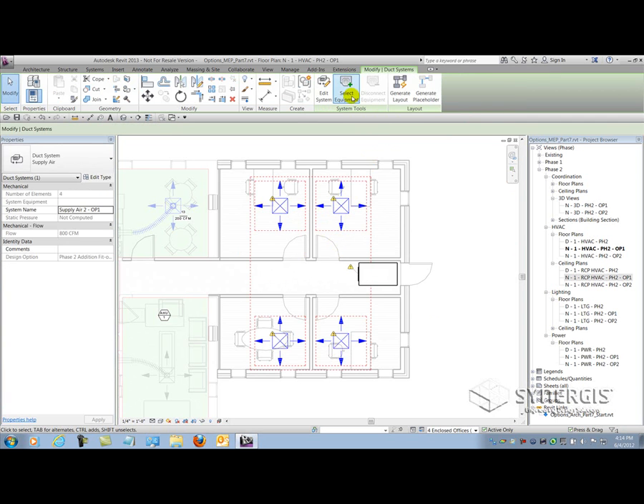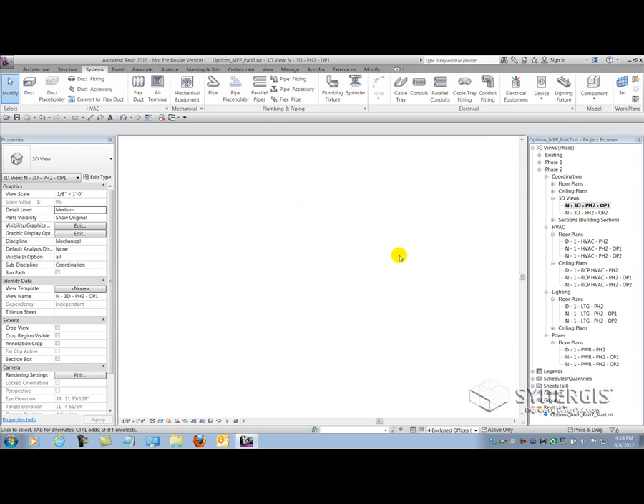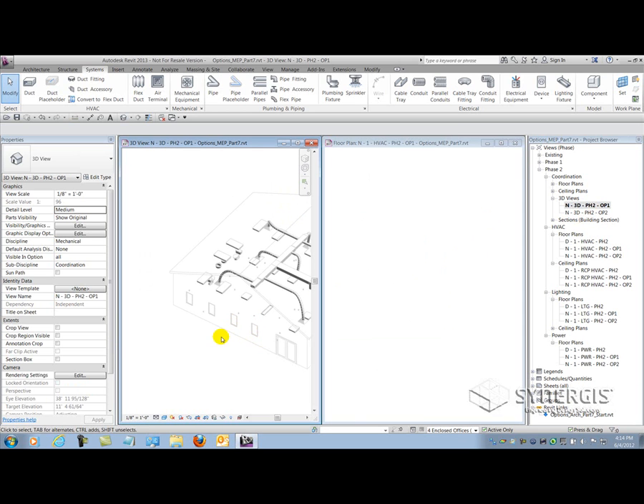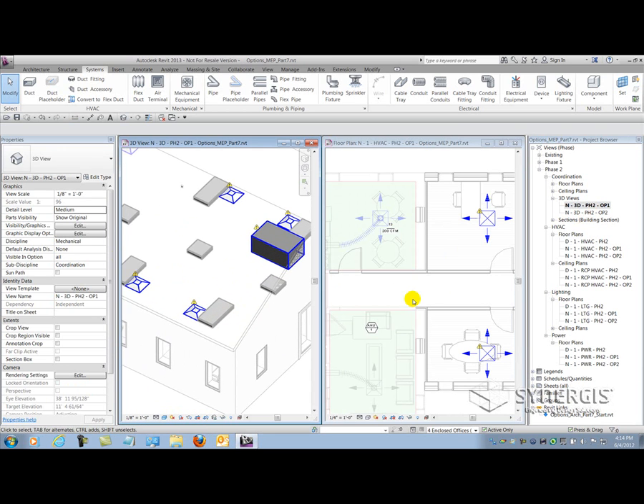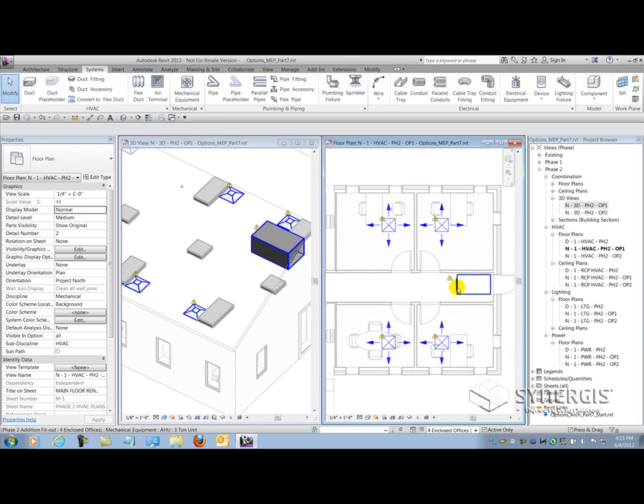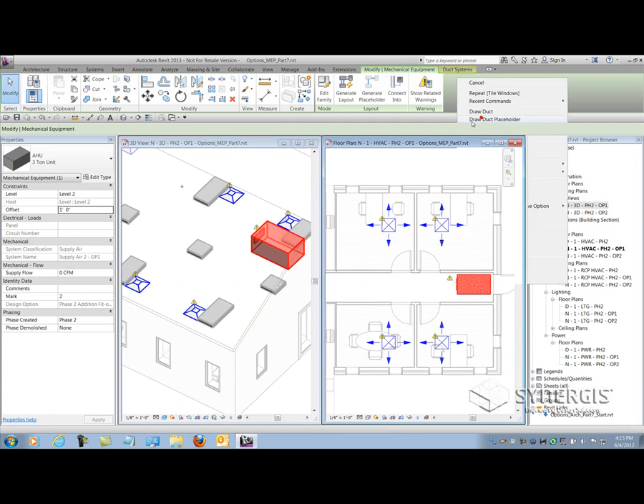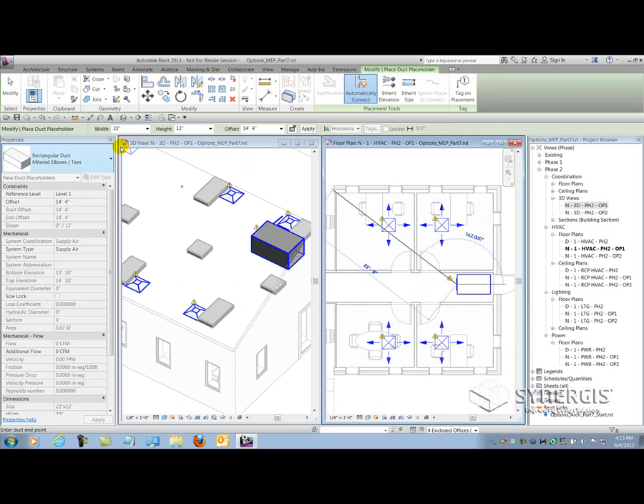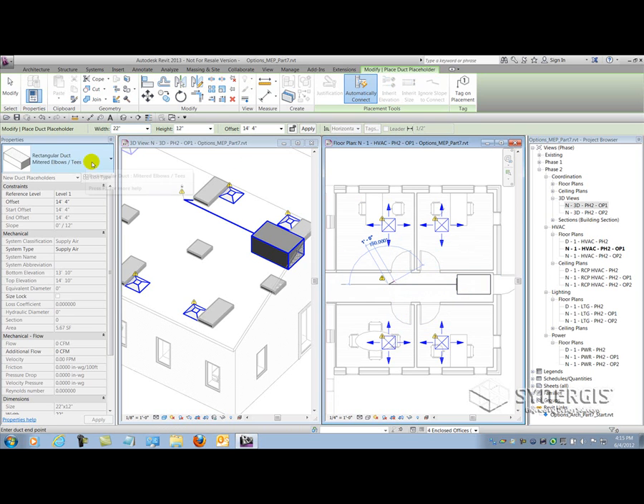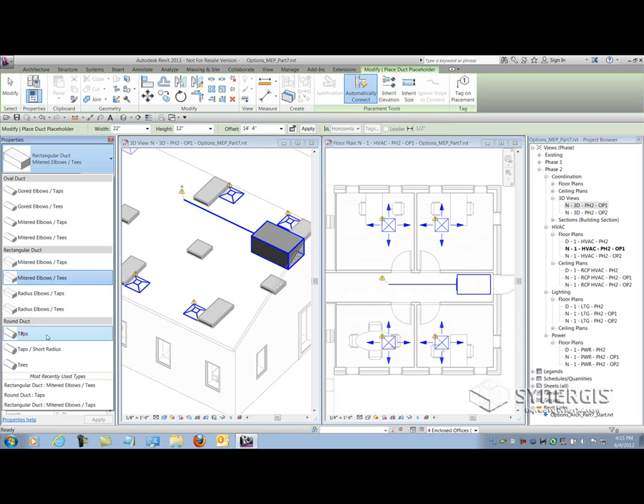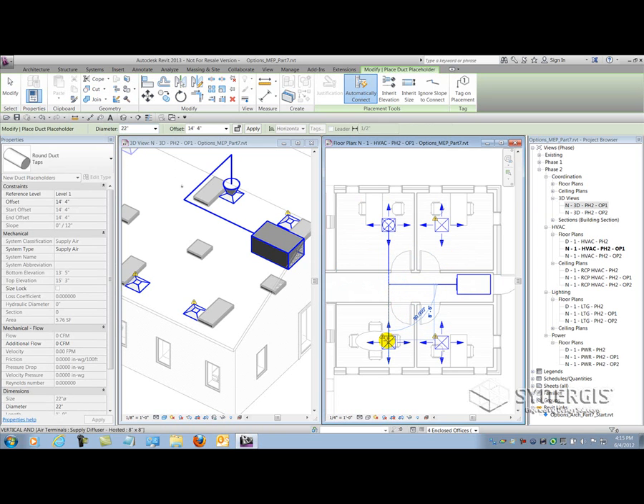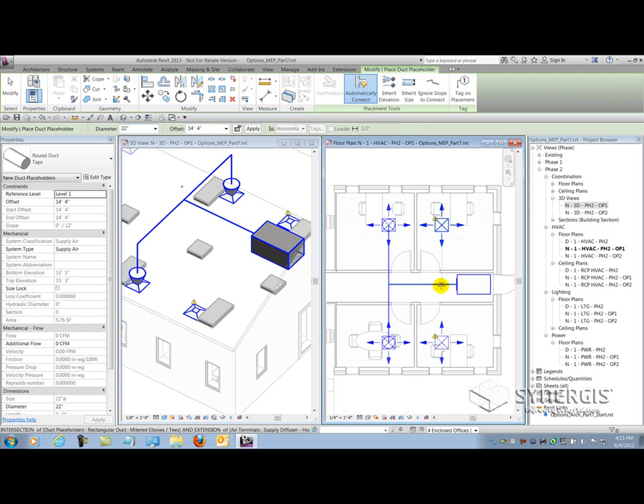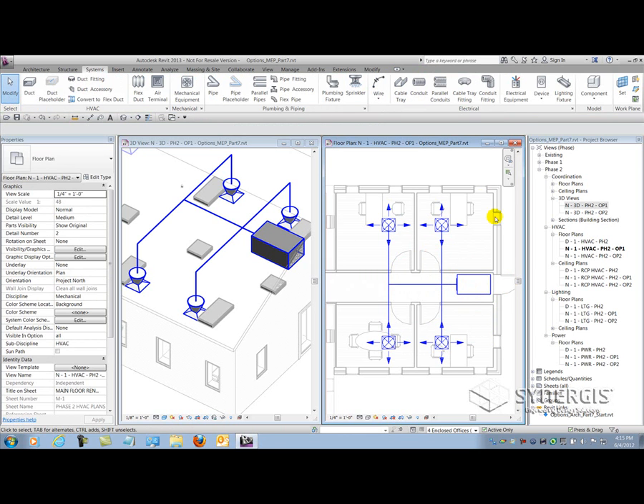Now that I have that set up, I can maybe lay out some placeholder duct to kind of give the architect an idea where duct runs would go. I'll just use the ducting tool for placeholders, but before I do that, let me create a system. I'll just pick my air terminals in my view and create a duct system and I'm going to call it Supply Air 2 for option number one. Then I'll select my equipment so that the system browser can track the connectors and then I'm ready to lay my placeholder duct out. I'll pick the connector on the mechanical equipment, right click and select Draw Duct Placeholder. I'll just use mitered elbows with T's for now and draw my duct out at the appropriate elevation. I want to change to round duct with taps for my branch ducting. As you can see as I place my branch ducting it's showing it over in the 3D view. That's option one for duct.